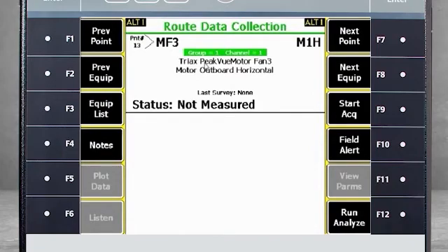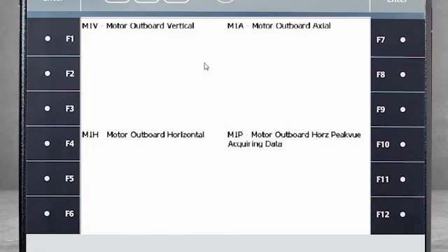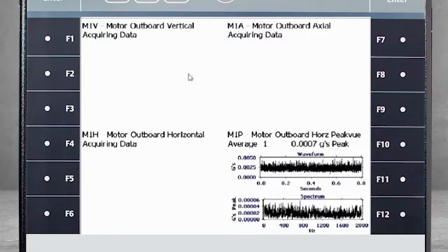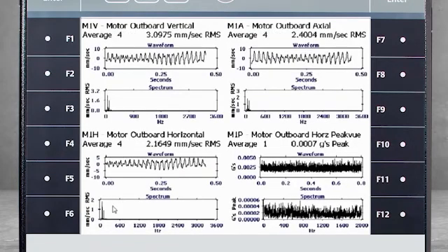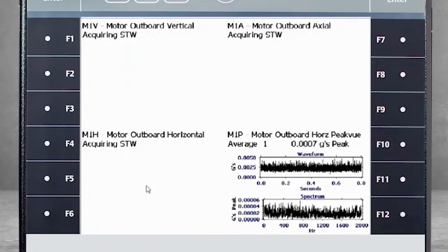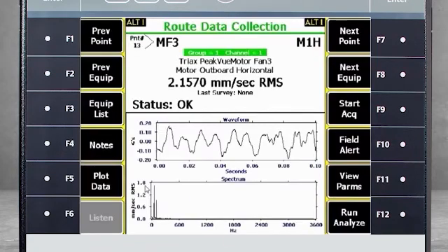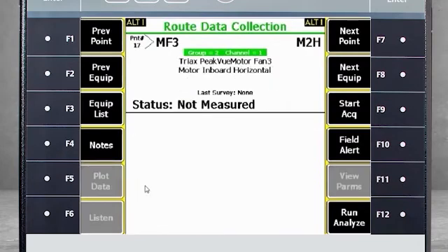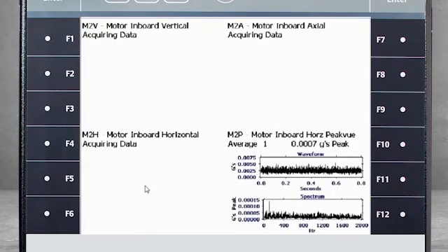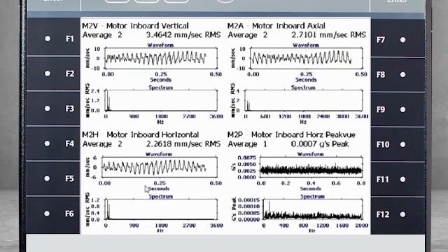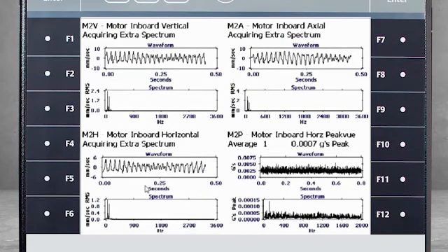Next, we'll collect data using the same configurations for triax sensors, but with the additional PeakVue measurement. This time when I push Enter, four points are collected in this plane before moving on to the next plane. Note that during data collection, the AMS 2140 shows spectra and waveform for the four points, so you are seeing a total of eight plots.